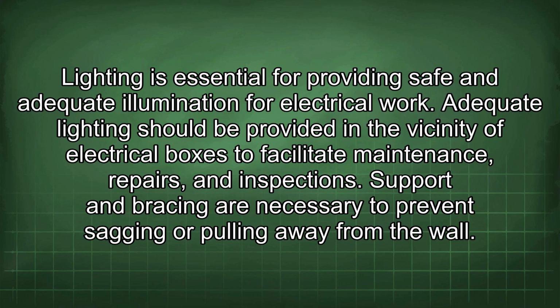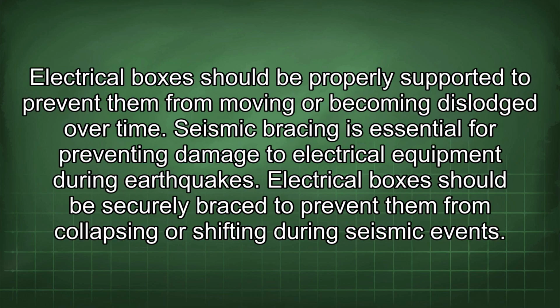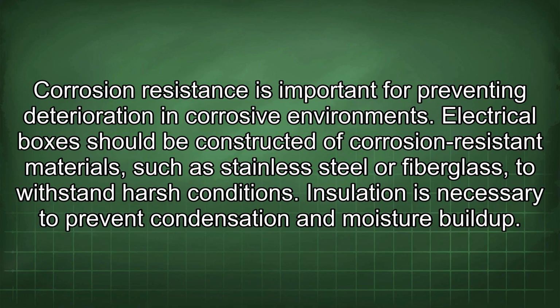Support and bracing are necessary to prevent sagging or pulling away from the wall. Electrical boxes should be properly supported to prevent them from moving or becoming dislodged over time. Seismic bracing is essential for preventing damage to electrical equipment during earthquakes. Electrical boxes should be securely braced to prevent them from collapsing or shifting during seismic events. Corrosion resistance is important for preventing deterioration in corrosive environments. Electrical boxes should be constructed of corrosion-resistant materials such as stainless steel or fiberglass to withstand harsh conditions.